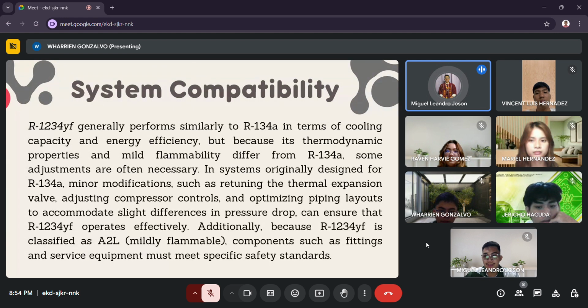Lastly, the system compatibility. R-1234yf generally performs similarly to R-134a in terms of cooling capacity and energy efficiency. But because its thermodynamic properties and mild flammability differ from R-134a, some adjustments are often necessary. In systems originally designed for R-134a, minor modifications such as changing the thermal expansion valve, adjusting compressor controls, and optimizing piping layouts to accommodate slight differences in pressure drop can ensure that R-1234yf operates effectively. Additionally, because R-1234yf is classified as A2L or mildly flammable, components such as fittings and service equipment must meet specific safety standards.